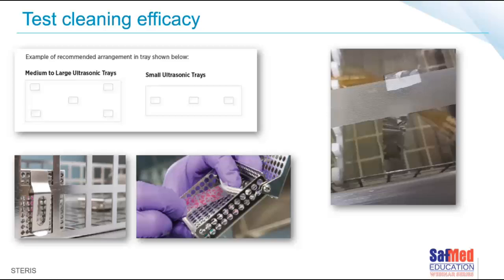We would put this in with a normal cycle, and at the end of the cycle the indicator should also come clean. Ideally, we want to place these indicators throughout the bath, because we want to make sure that all of those transducers are working. If you only have one indicator, make sure you move it around to the different areas. Ideally, perhaps on the first cycle of the day, you use more than one indicator, because we're testing to see if all those little pumps, all the transducers, are in fact doing their job. That's why we looked at them from underneath, so that we could see what they look like.